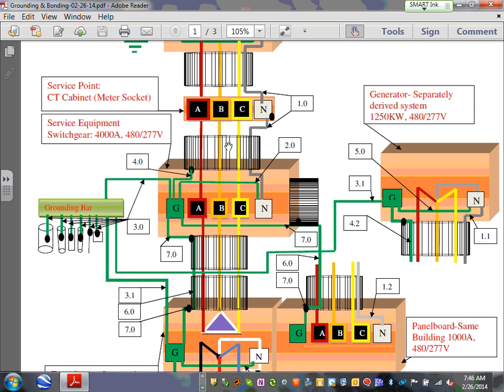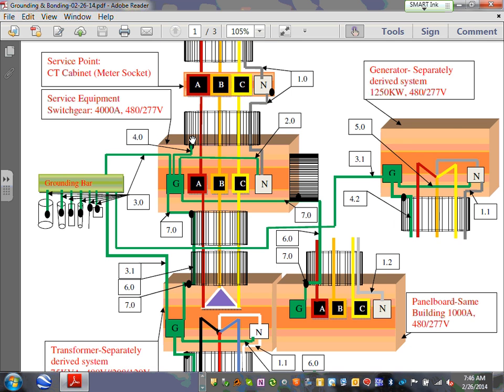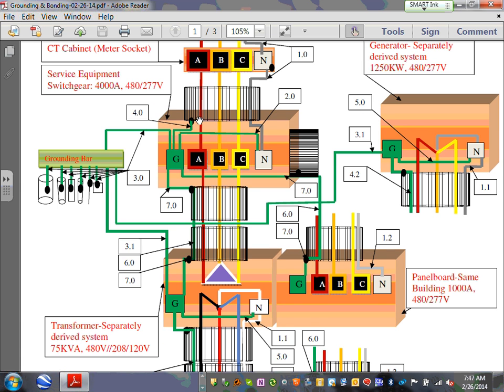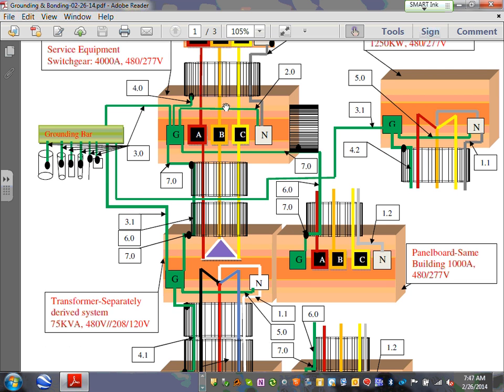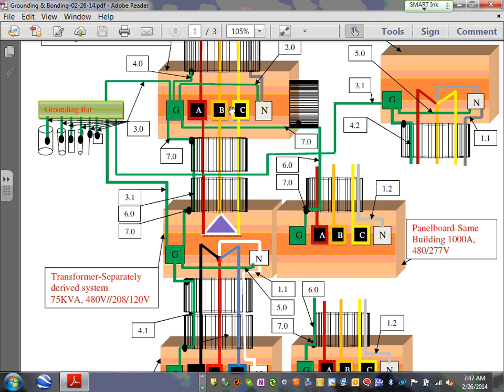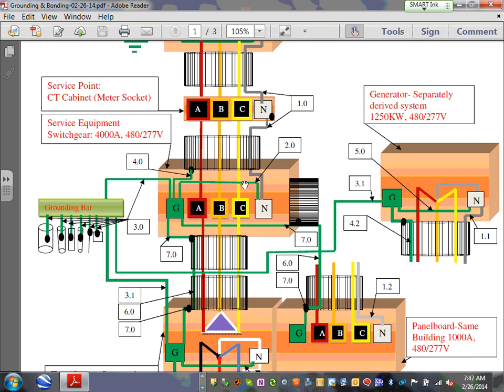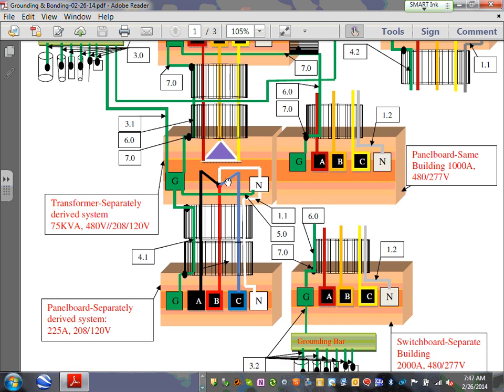Now, out of the termination box, you bring the power. When I say bring the power, I mean bring conduits and wires from the transformer to the termination box, and from the termination box into the first switchgear, the service equipment. The service equipment here is 4,000 amp, actually identical to the service equipment, Karen, that we have in our building, 4,000 amp. Inside the service equipment, right here, that's your service equipment. Then you take a feeder right down here.